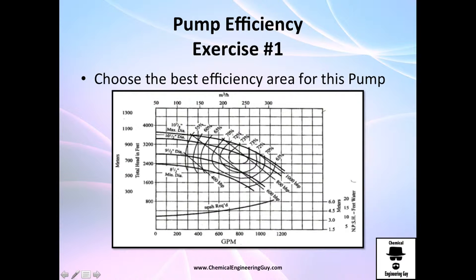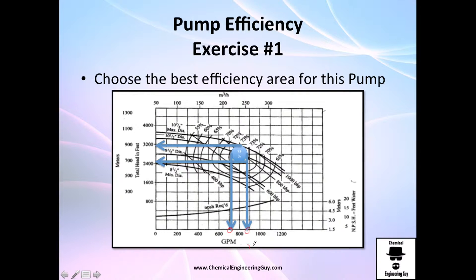We're going to do only two basic exercises on pump efficiency. Number one, we have this diagram from our pump supplier, and maybe your boss told you to find the best optimal efficiency points. This is very easy — it's the 73% region right here. This area will be the best to operate, so as you can see, between 700 and 900 gallons per minute this pump will be operating very well.